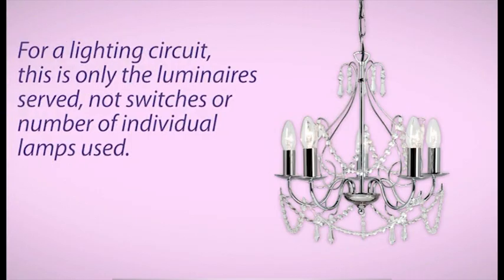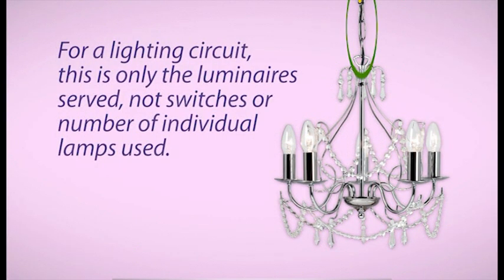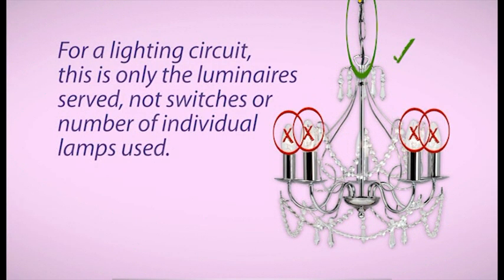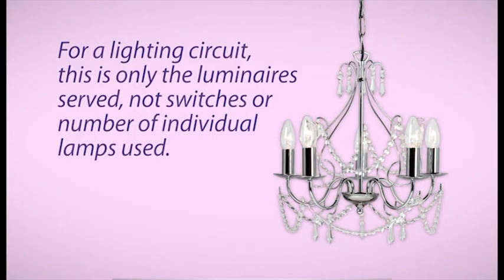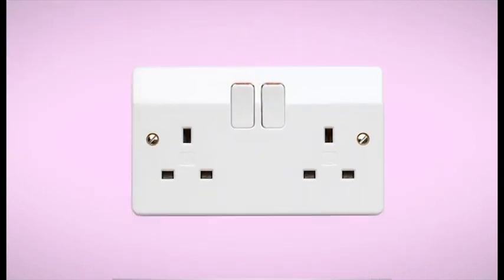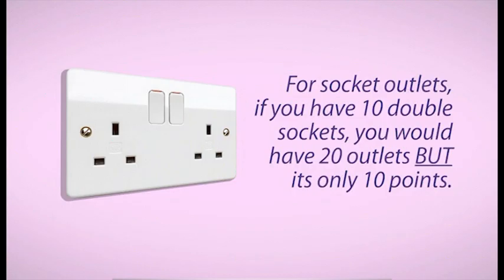Next, we have number of points served. Now this is referring to the termination of the fixed wiring intended for the connection of current using equipment. For a lighting circuit, this is only the luminaires served, not switches or number of individual lamps used. And for socket outlets, if you have 10 double sockets, you have 20 outlets, but it's still only 10 points.